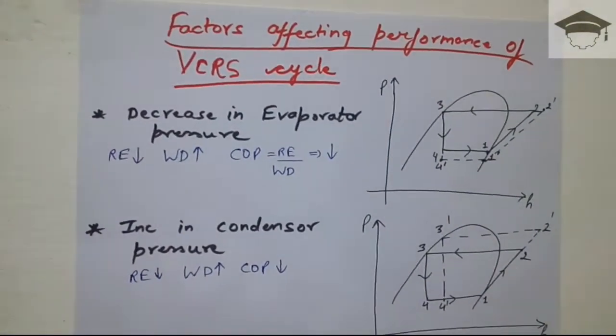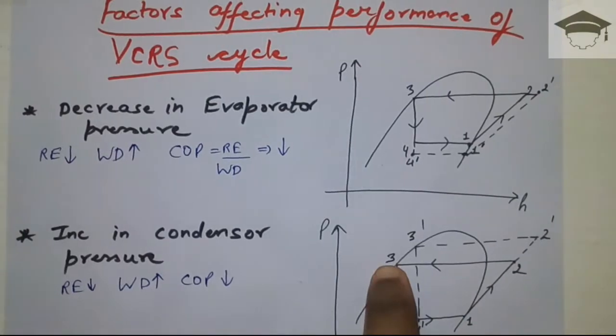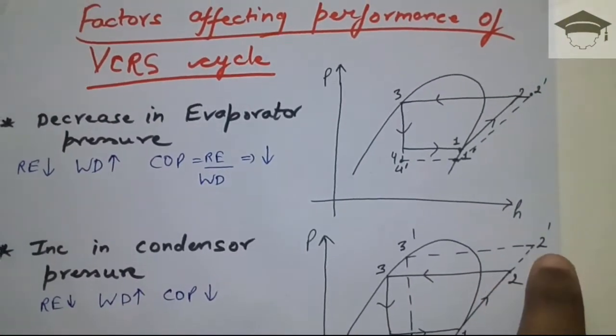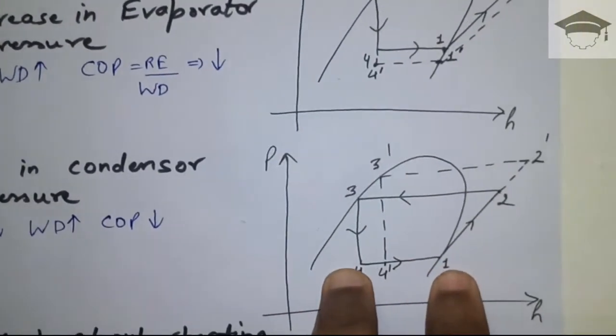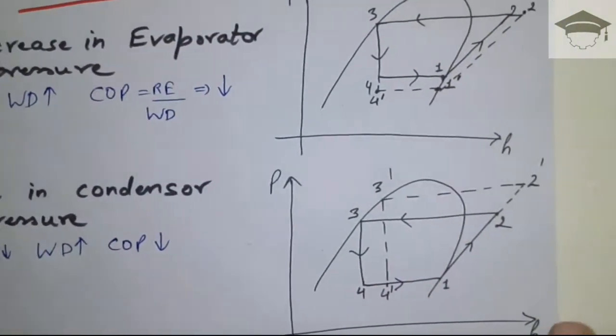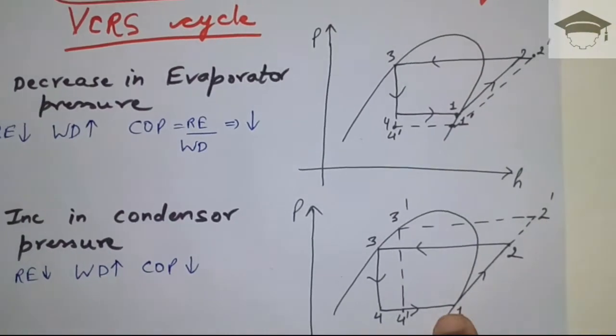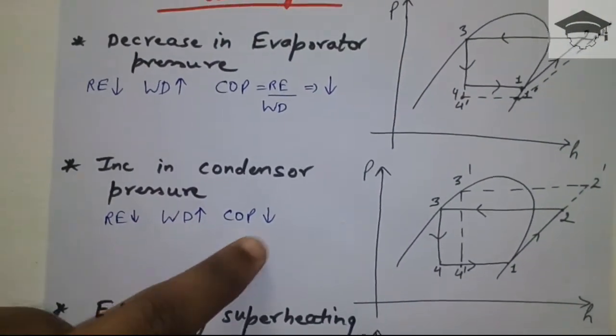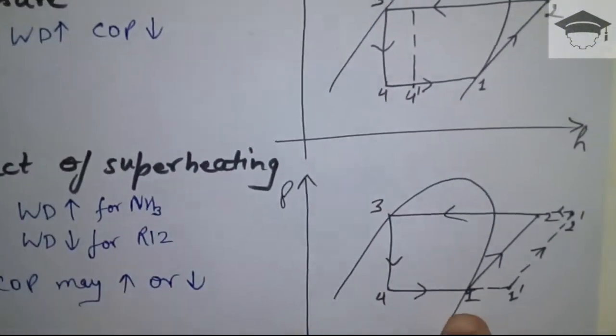Moving on to the second parameter: condenser pressure. The condenser pressure line is the solid line. If we increase the condenser pressure, shown by the dotted line from 2 dash to 3 dash, the refrigeration effect is reduced from h1 minus h4 to h1 minus h4 dash. The work input also increases from h2 minus h1 to h2 dash minus h1. As with the previous case, refrigeration effect is reduced and work done is increased, so COP is reduced.